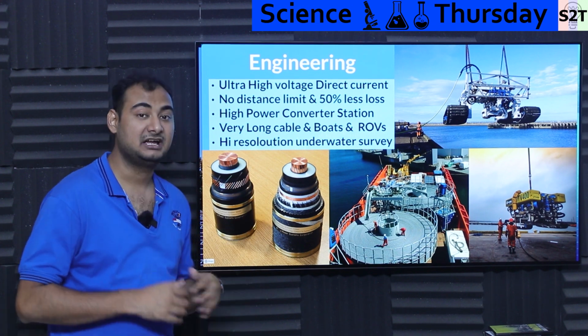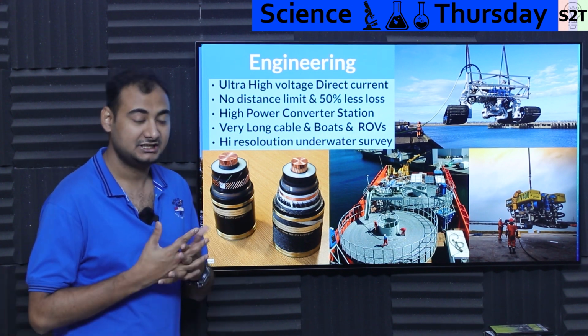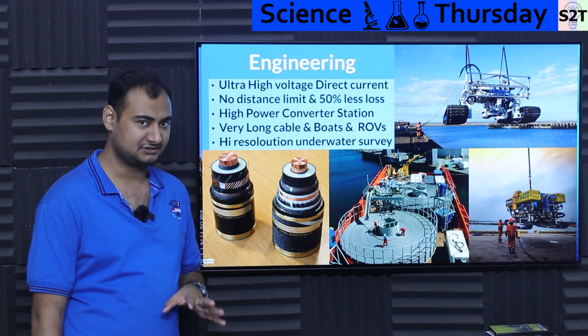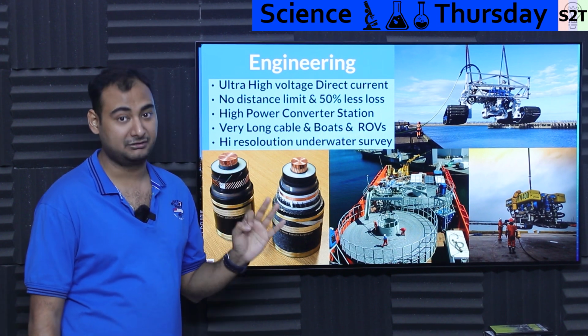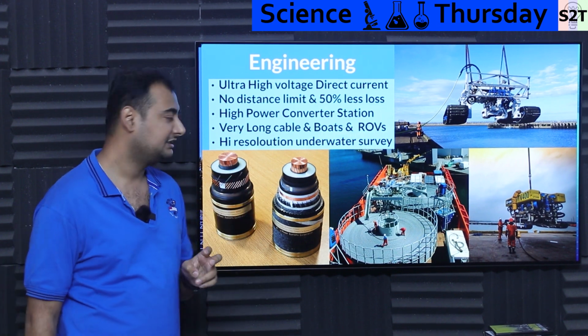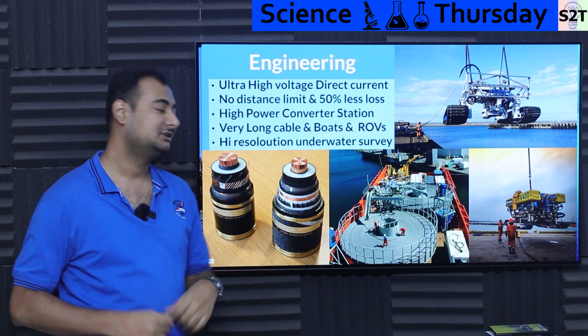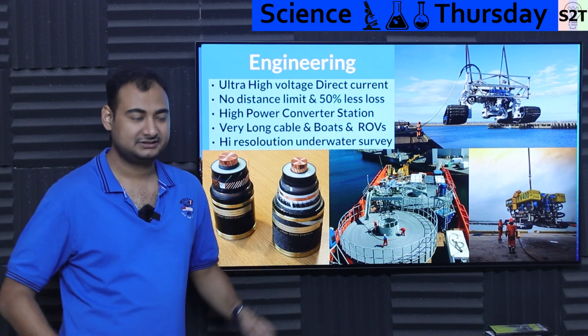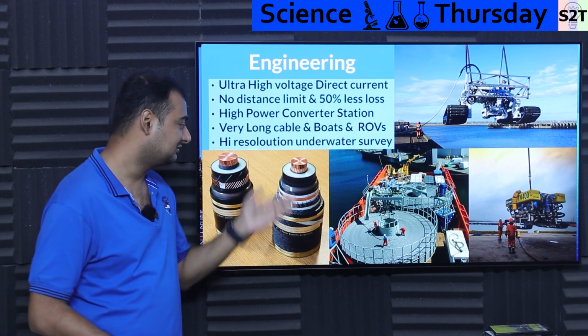Be mindful, DC has much more brutal requirements on the insulator compared to AC. That's one area where the insulator has to be perfect. And if you're talking ultra high voltage, insulation becomes thick. And if you're making that thick, you may think, hey, why not just make the core itself thicker?